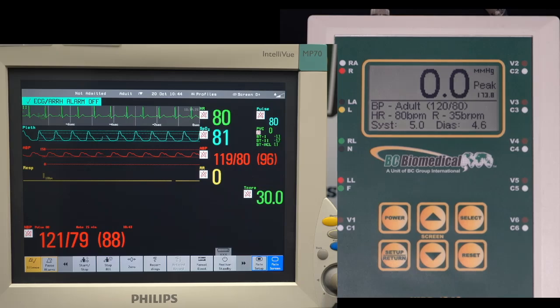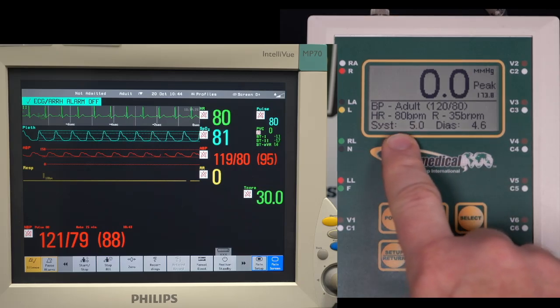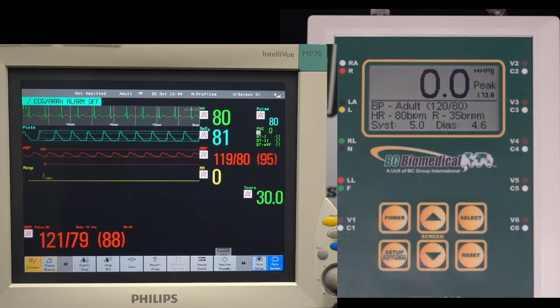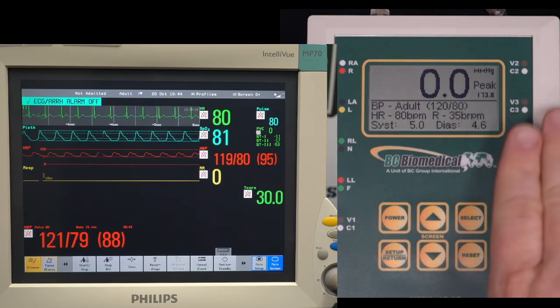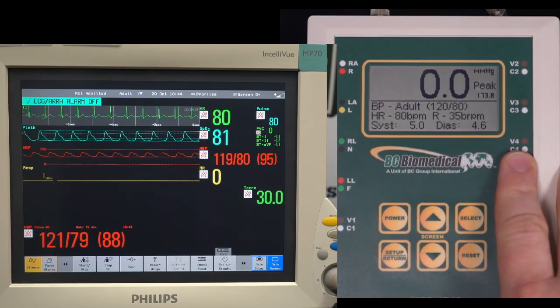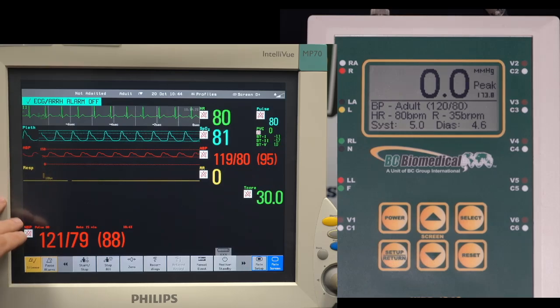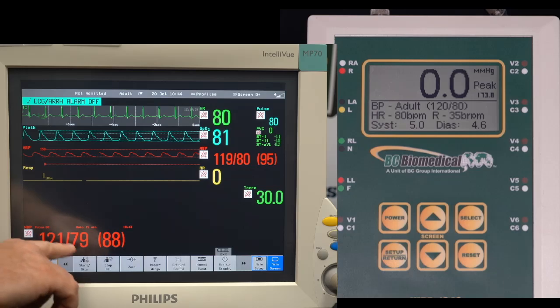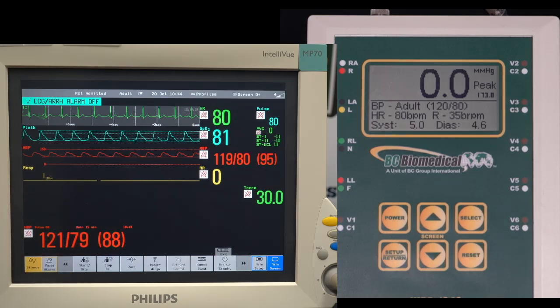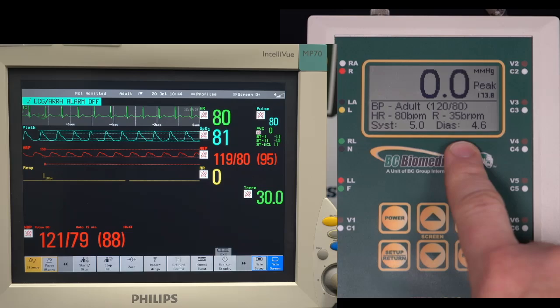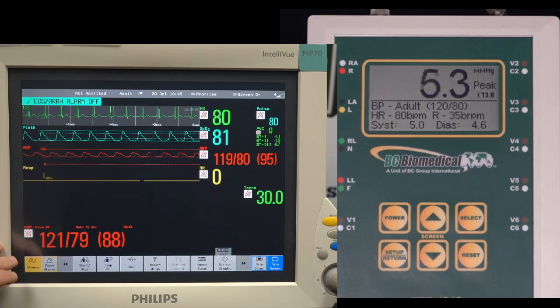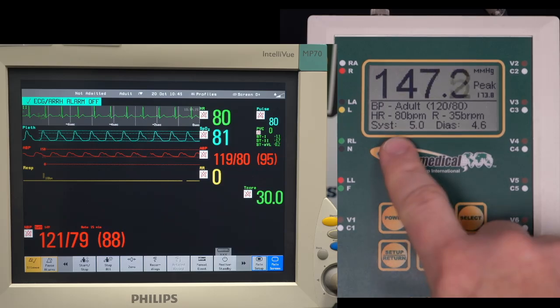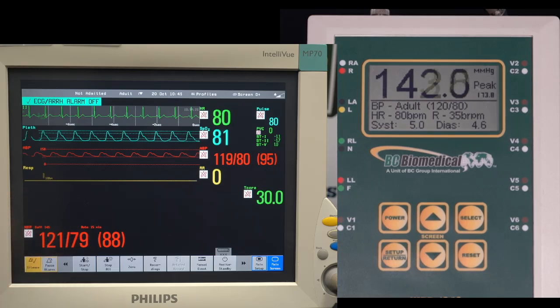So you'll see here on the settings on the screen, I have a systolic and a diastolic shift. What that allows me to do is tweak the algorithm, tweak the output from the NIBP to match the monitor that I'm testing. And so now we can see I get really close to my 120 over 80. Now, what I would want to make sure is that every Philips monitor, I would always set it to the same settings when I use Philips, and I should always get 120 over 80. Now, if I go and test another brand, then I may need to change those settings to something else. Okay, so that's the offset setting, and it's running another simulation here.